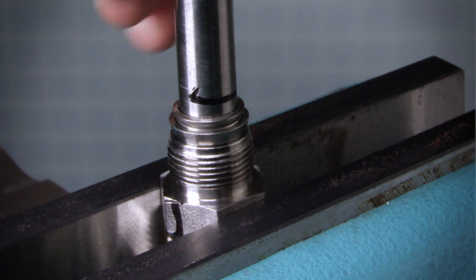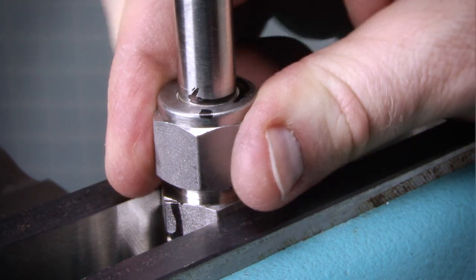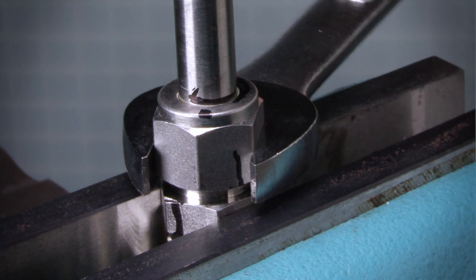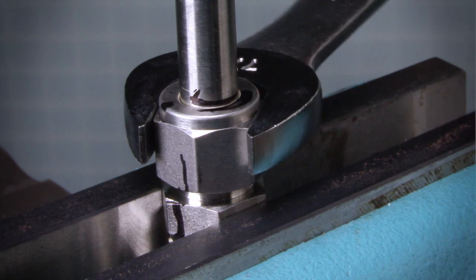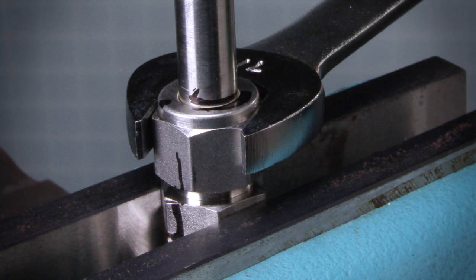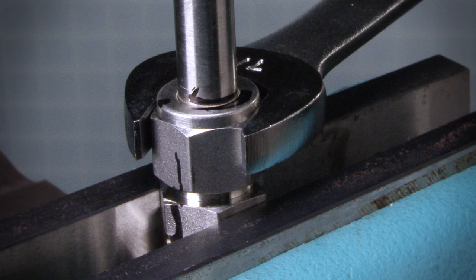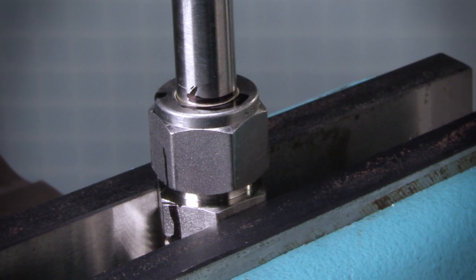Insert the tube with pre-swaged ferrules into the fitting until the front ferrule seats against the fitting body. While holding the fitting body steady, rotate the nut with a wrench to the previously pulled up position, as indicated by the marks on the tube and flats. At this point, you will feel significant increase in the resistance. Tighten the nut slightly.